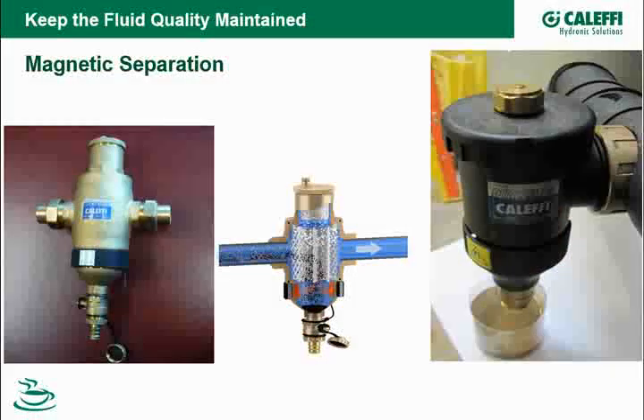Magnetic separation. This is becoming more and more important. We do a good job with most of the different type of separation and filters that are out there now, and Y strainers are getting big dirt chunks and debris out. But these fine little particles that can be coming out of a system that does have non-barrier tubing in it, a magnetic type of separator will get a lot more of that fine particle out than you can with just the media that's inside there.